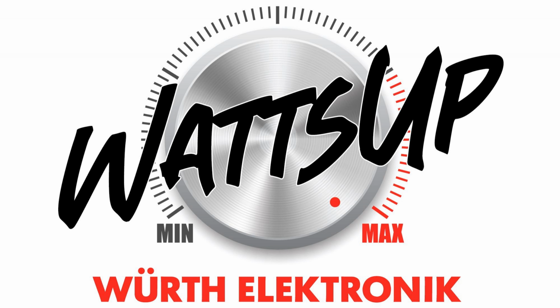As you can see, the combination of harsh conditions and voltage damaged the components. We were happy to find out that the components could handle the harsh environment when they had no voltage. We were also pleased to see that the THB parts did not suffer any significant degradation even after a harsh test.